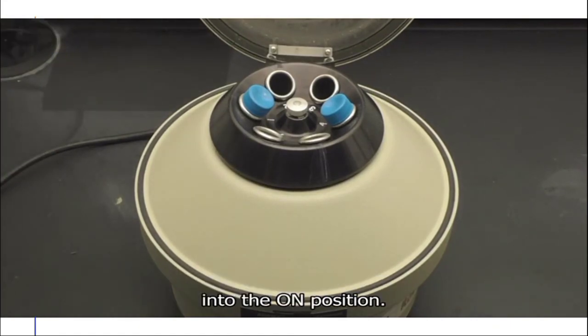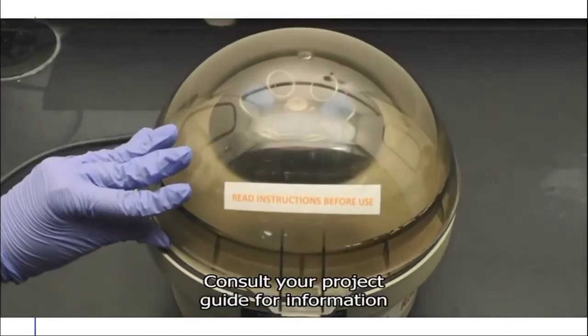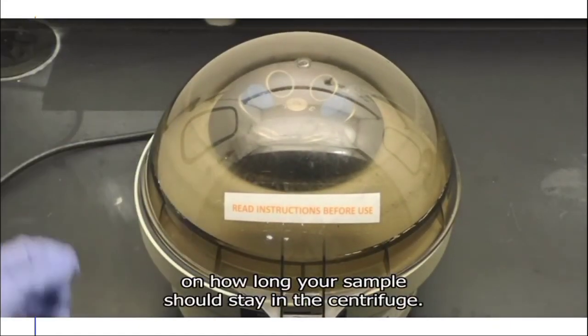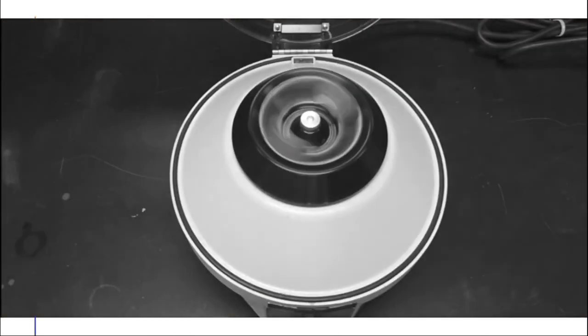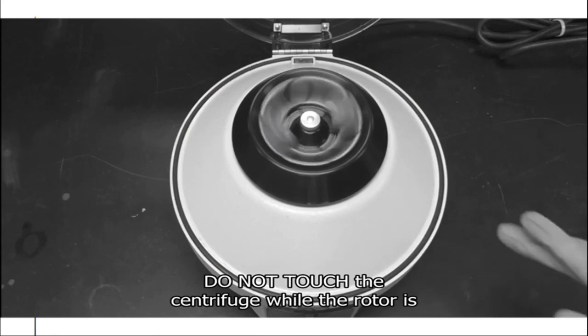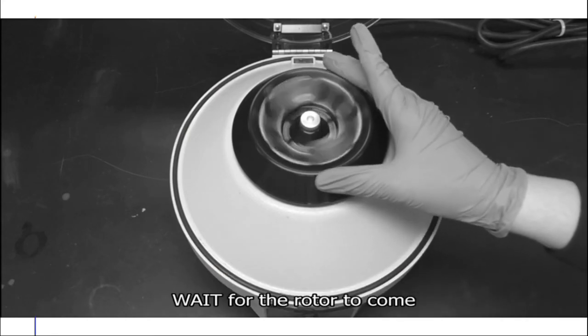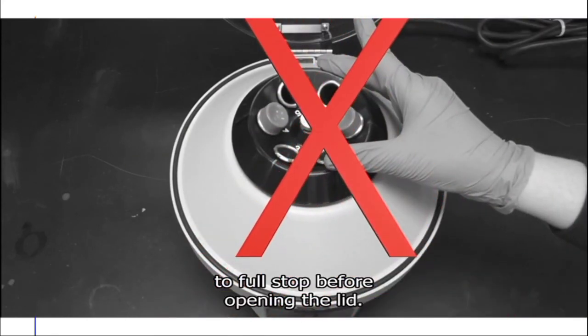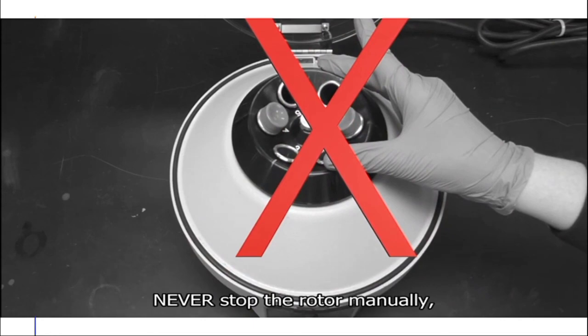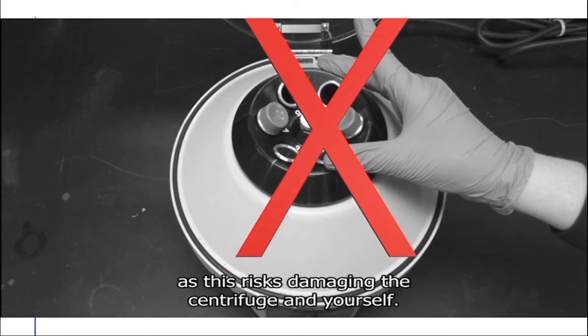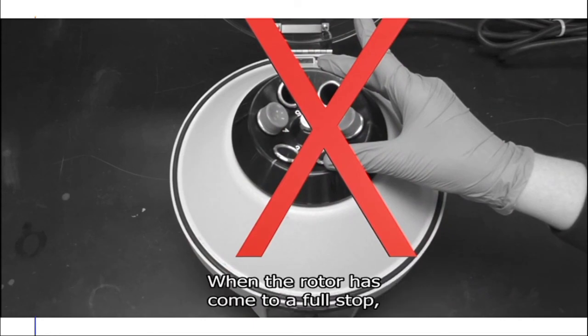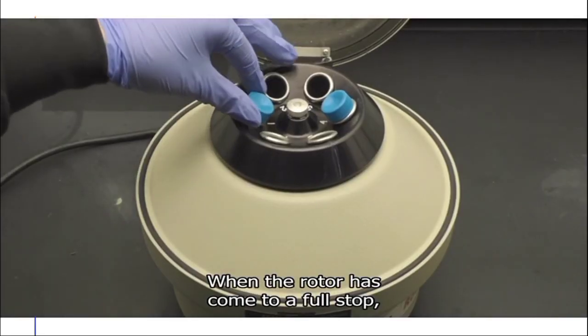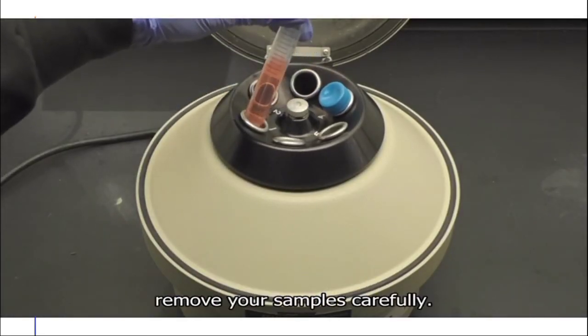Shut the safety cover and move the toggle switch into the on position. Consult your project guide for more information on how long your sample should stay in the centrifuge. Do not touch the centrifuge while the rotor is still spinning. Wait for the rotor to come to a full stop before opening the lid. Never stop the rotor manually, as this risks damaging the centrifuge and yourself. When the rotor has come to a full stop, remove your samples carefully.